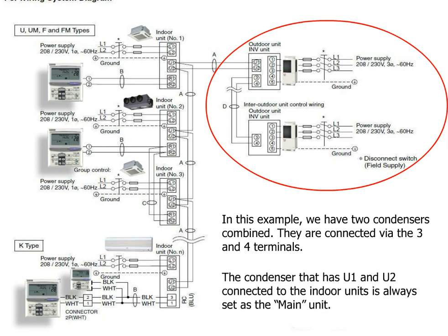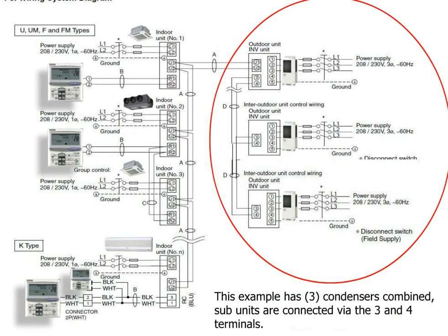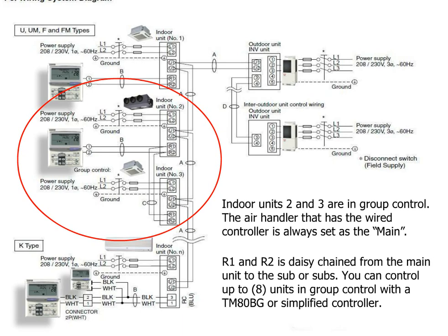The condenser that has U1 and U2 connected to the indoor units is always set as the main unit. The 63 series can combine up to 3 condensers. Sub-units are always connected via the 3 and 4 terminals. Indoor units number 2 and 3 are in group control.